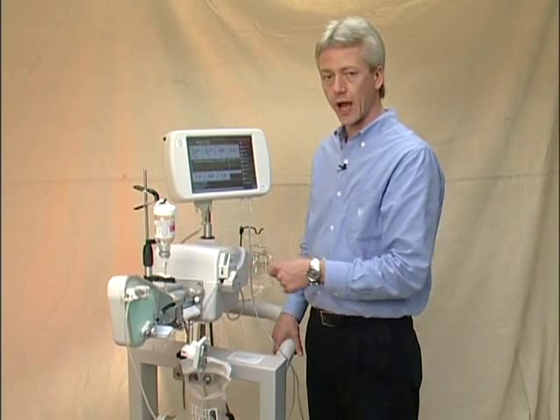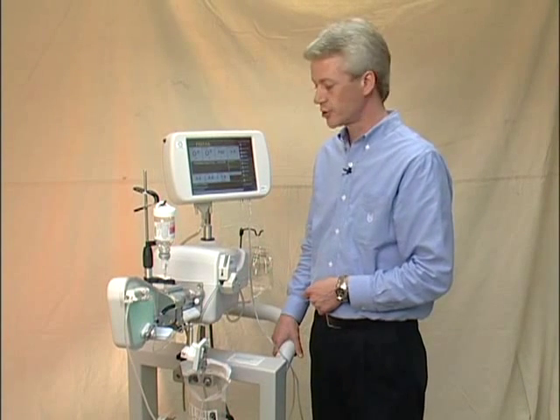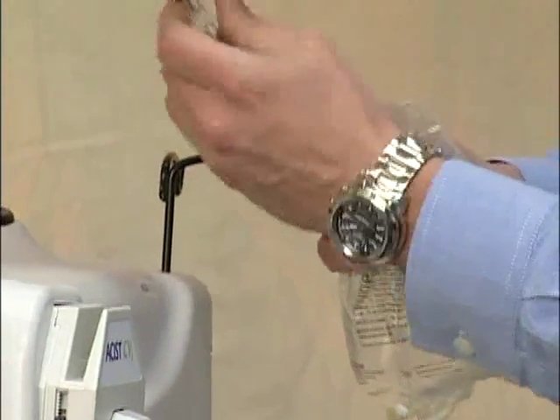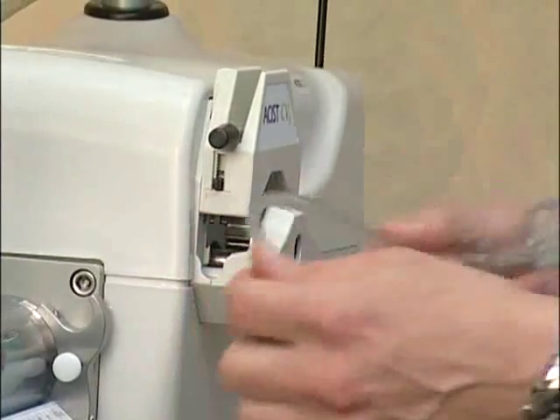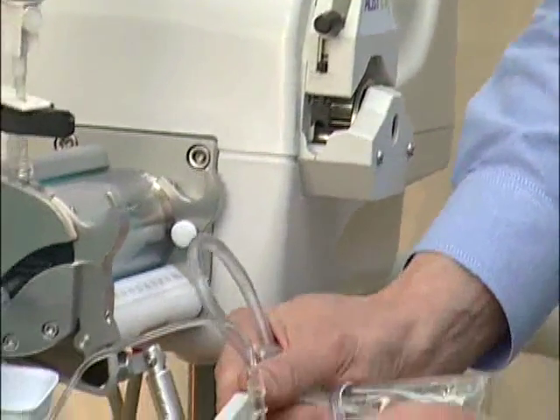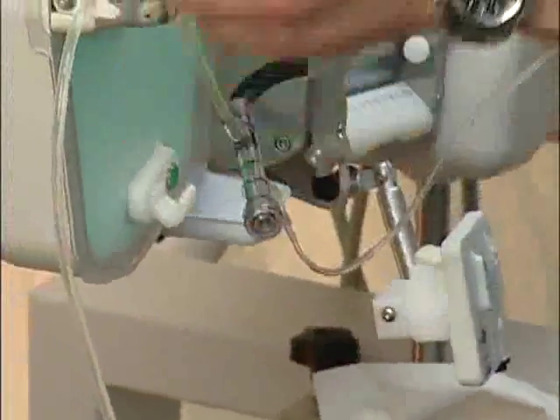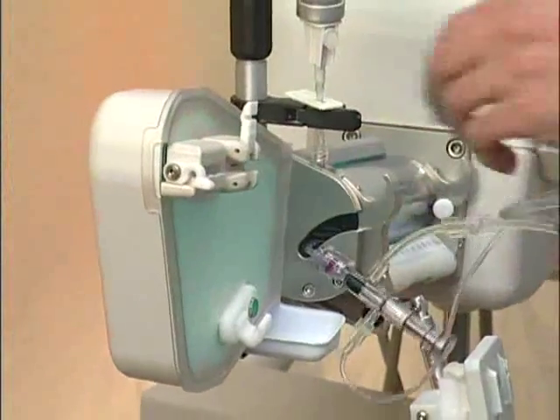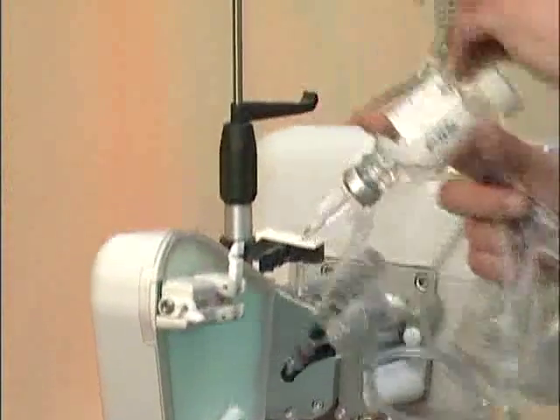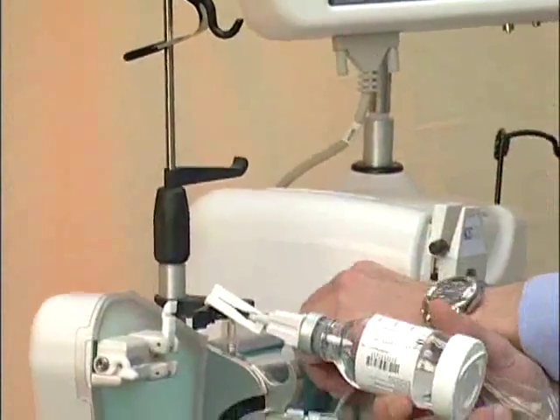The RAM will move backwards and disengage the wiper, which then allows me to remove all the disposable kits and discard them. We'll start with the saline bag, the hand controller, the tubing through the peristaltic pump, the transducer cartridge and the Med-X, the manifold, the air column detect tubing, the bottle, and finally the syringe.